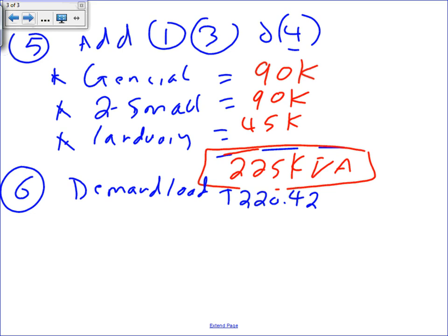If you guys look at this table, 220.45, let's start with the following. Here's what the table tells you. The first 3K, leave him alone. Then from 3,001 to 120K, cut them by 35 percent. Then this is very important, guys. How am I going to do that one? The first 3K, leave him alone.